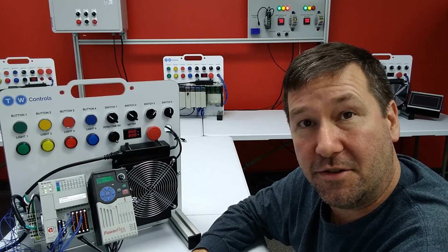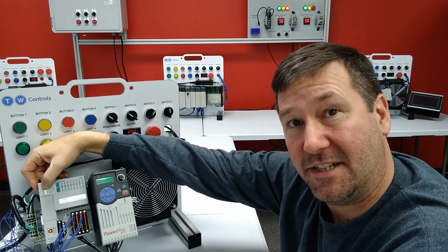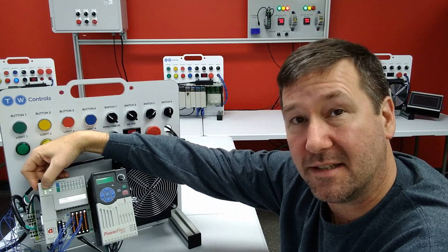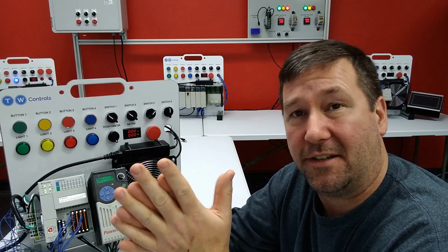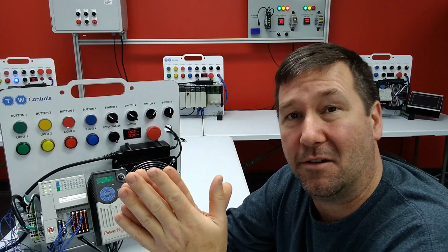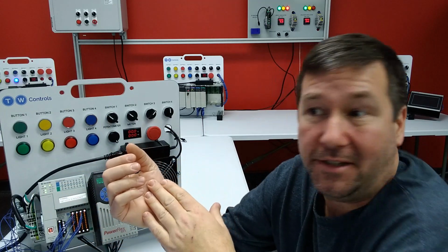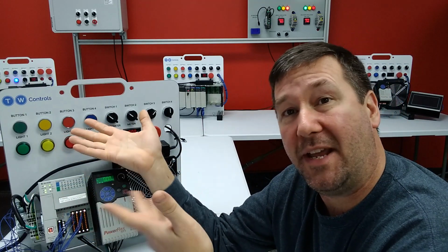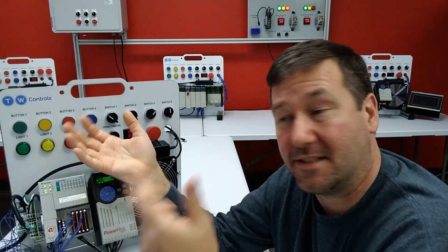One thing I caution you of is to pay really close attention to this I/O light. If it is flashing, even if it's flashing green, then something is wrong. We want a solid I/O light there. Now I say that, but honestly there are a lot of systems out there where it's not unusual to have an I/O light flashing. Maybe it has some portable fixturing that's not always in place, or maybe it's a big system and you may have something locked out from time to time to do maintenance and it's just offline.